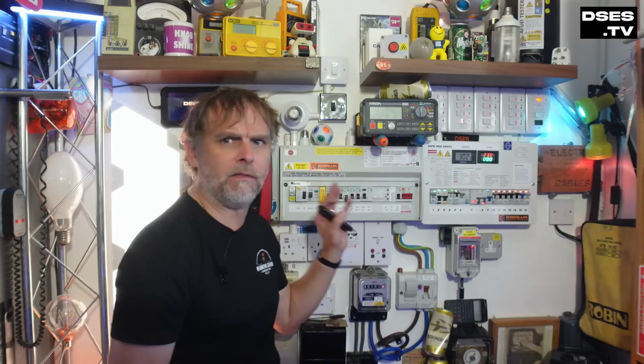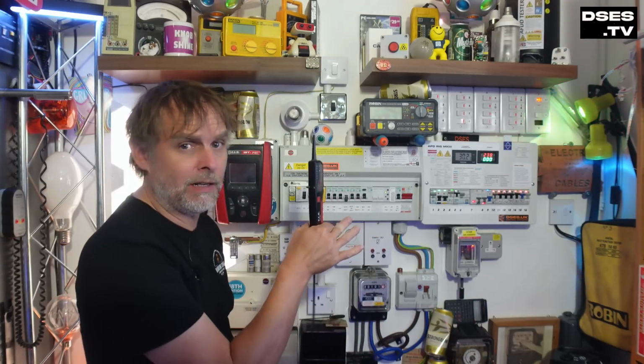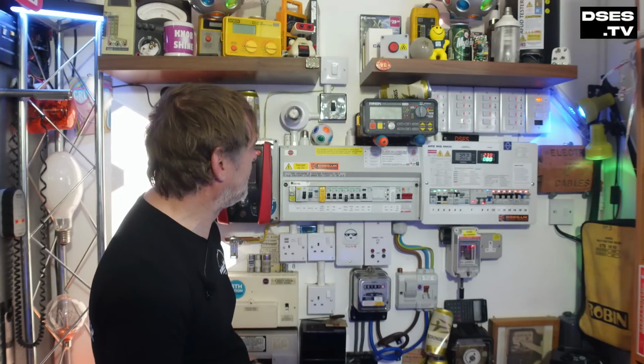That's reason number one why a voltage indicator is more suited for safe isolation than a multimeter. If I'd measured 115 volts, I'd be worried about what's gone wrong here and what I can even touch. But my dedicated voltage tester assures me, although there is a voltage present, it isn't strong enough to cause any real harm.